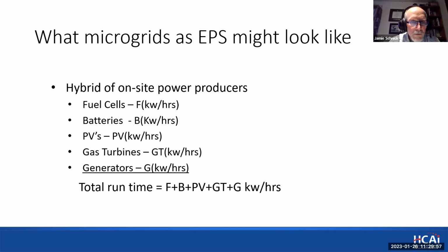Yes, and this is a great question, because this is a new concept, a new way of looking at runtime. We've always looked at the emergency side - NFPA 110 says you need fuel to operate the generator fully loaded, in this case for 6 hours. But the law only requires that you back up the actual load for 96 hours. So I think there's going to be new scrutiny, new calculations looking at how many kilowatt hours you need to get your 96 hours of operation.